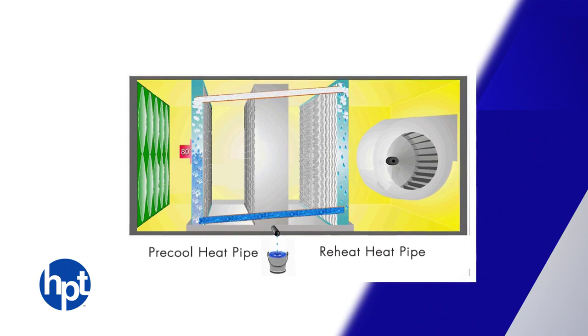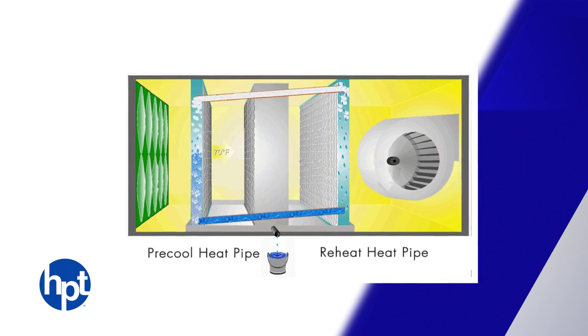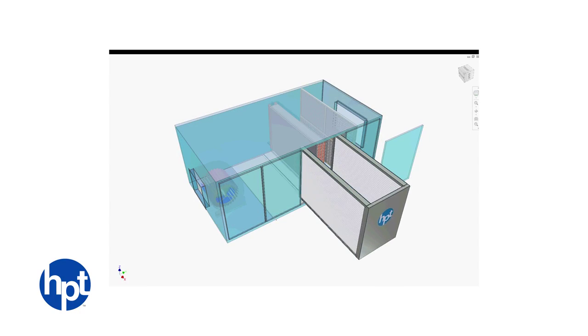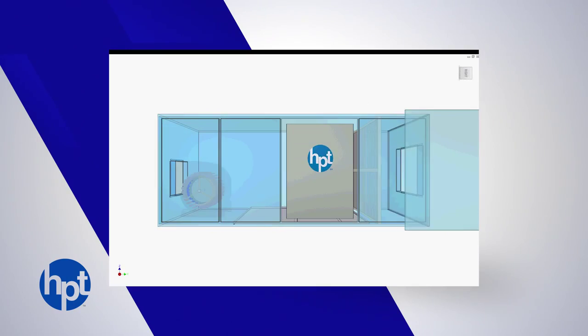When the league opted for a less stringent air condition of roughly 65 degrees Fahrenheit and 45% relative humidity, this allowed the design team to simply lower the chilled water set point while replacing the 12 indoor air handlers with new HPT heat pipes wrapped around a dual six-row cooling coil.